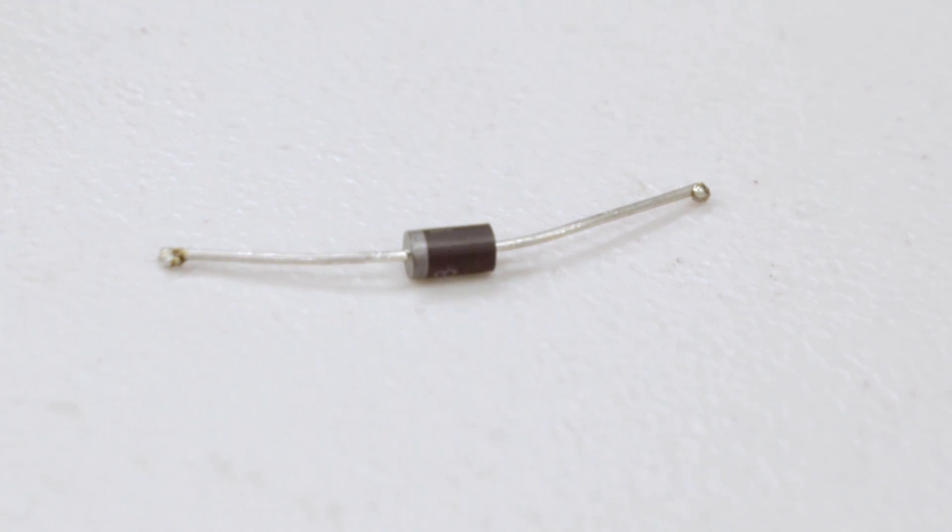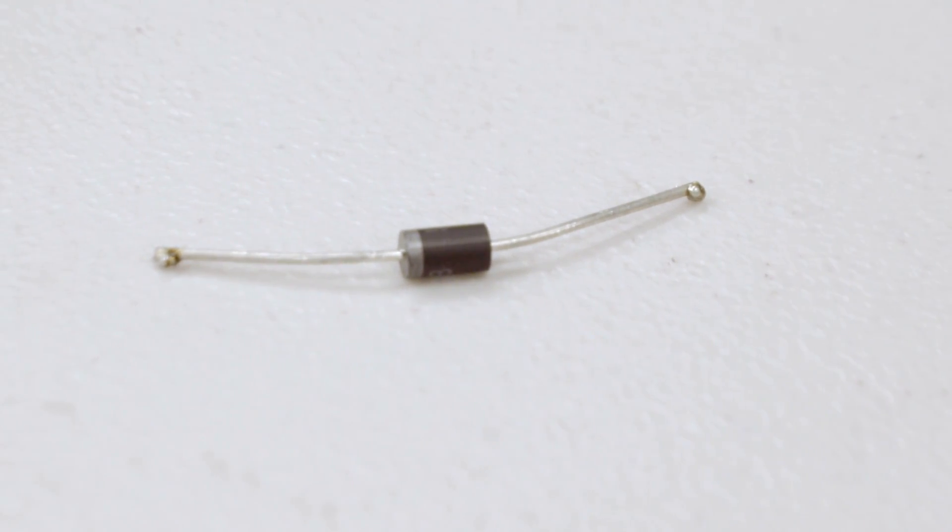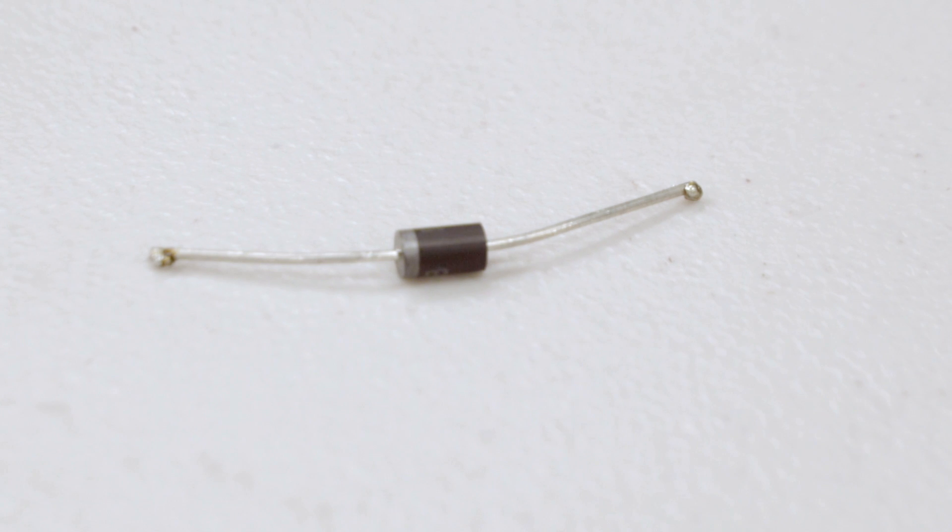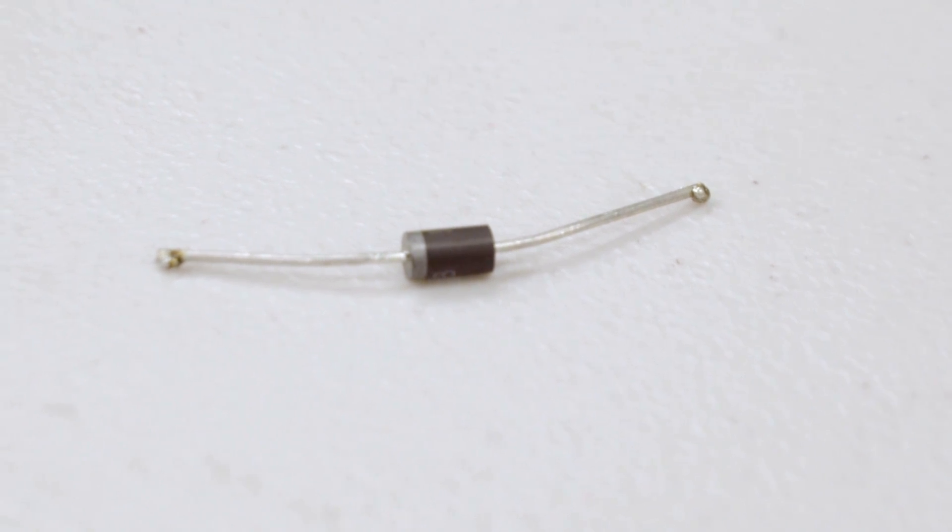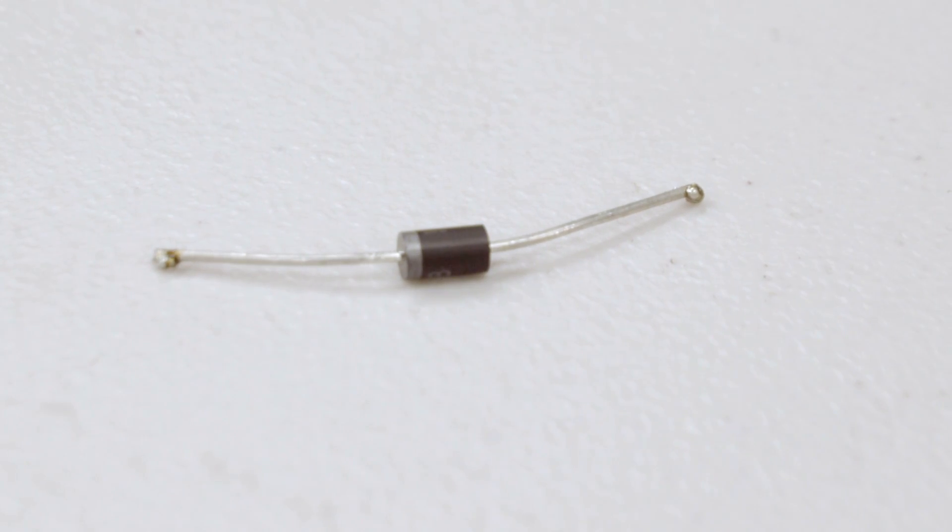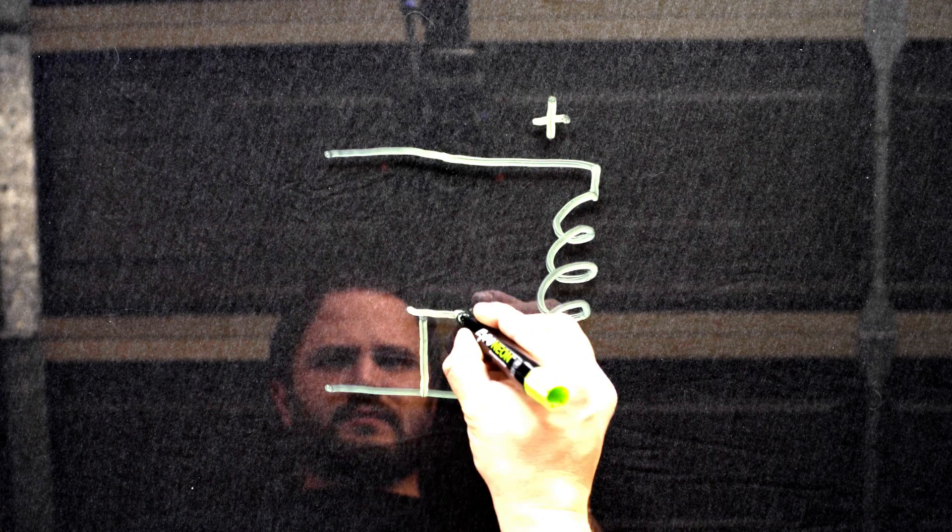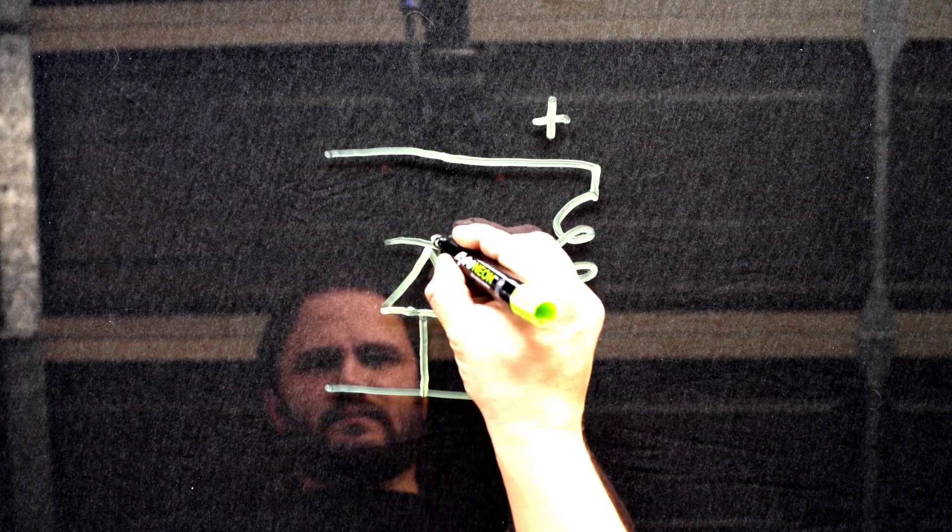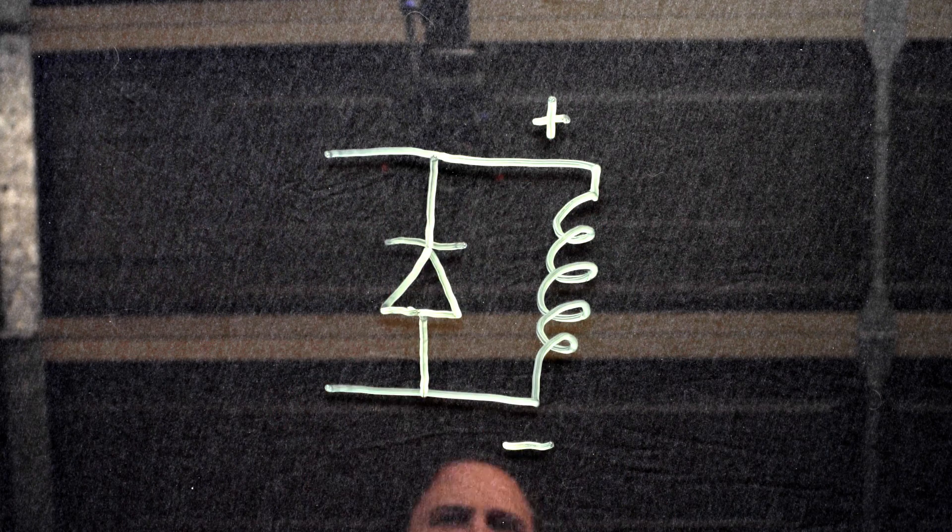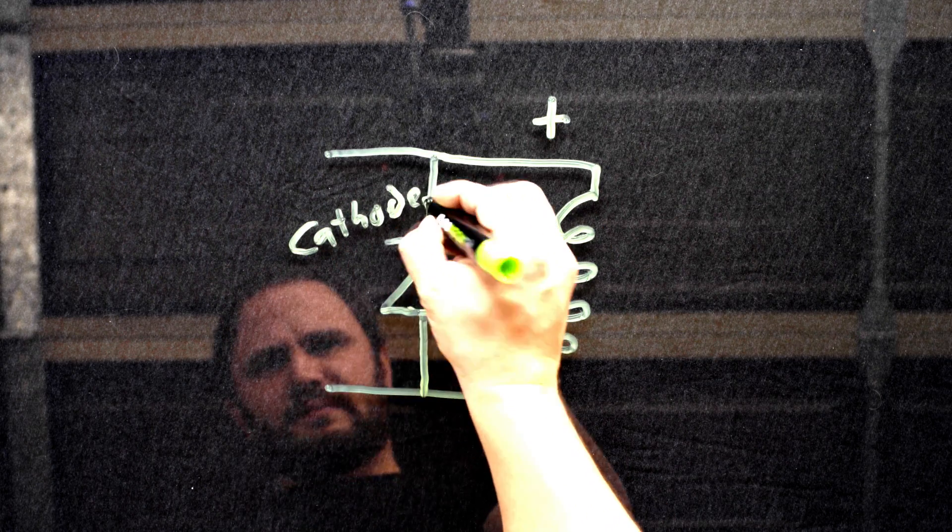To solve the back EMF problem with coils, standard practice is to connect a snubber diode across the coil. Also known as a flyback diode, this diode is connected from the positive side of the coil to the negative side. That is, the cathode connects to the positive wire of the coil, the white strip faces positive, and the anode connects to the negative wire.